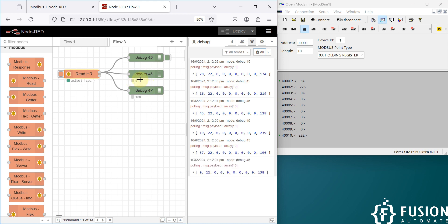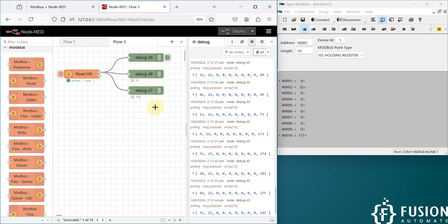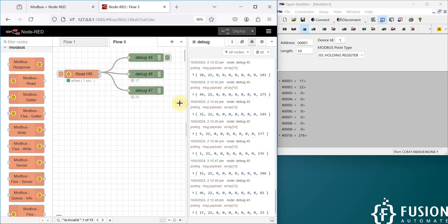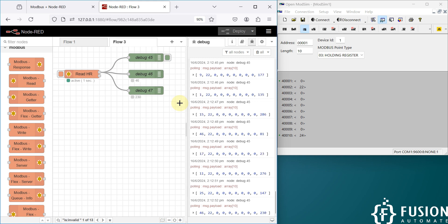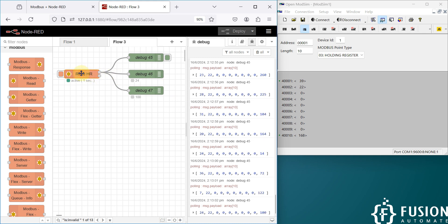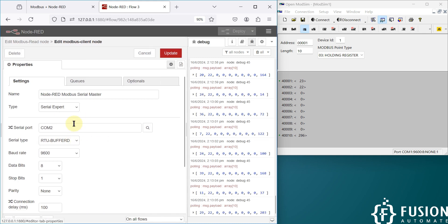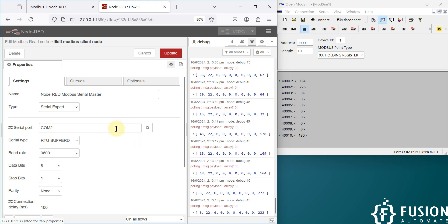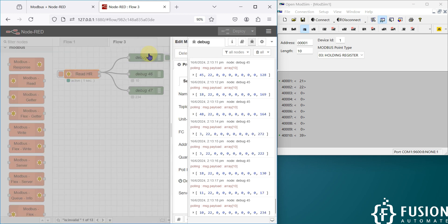This is how you can use Node-RED to read data from any Modbus serial device — whether it's a physical Modbus serial device or a simulated one. If it is a physical Modbus serial device, you have to use an RS485-to-USB converter, plug that USB into your system, and then choose the COM port. Once you plug in the USB, you will see the available COM ports. Verify which COM port your USB is connected to and use that COM port to read data from the device.